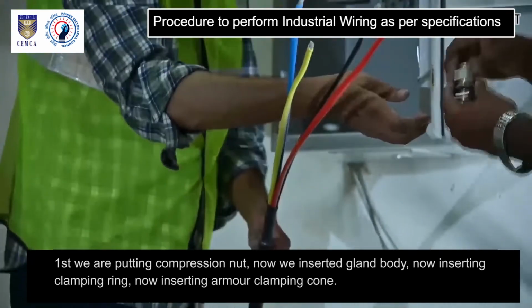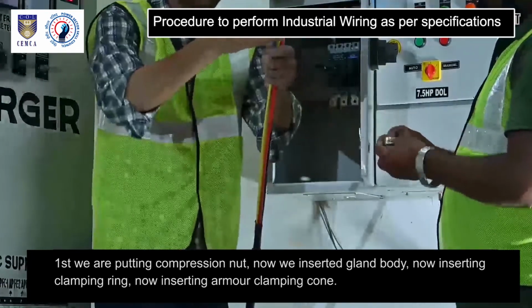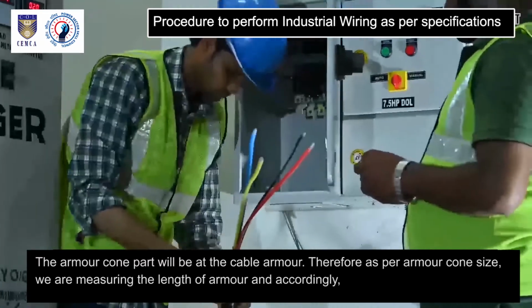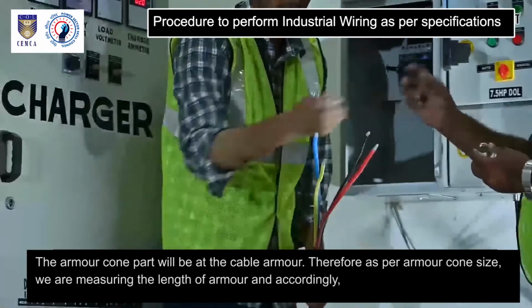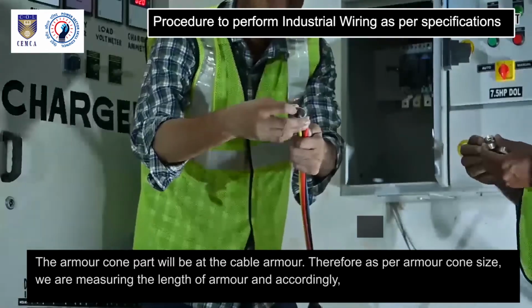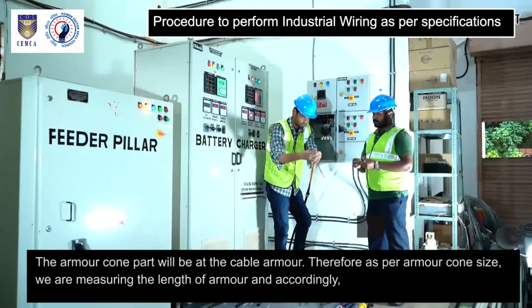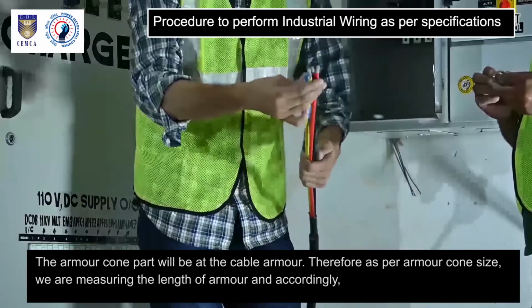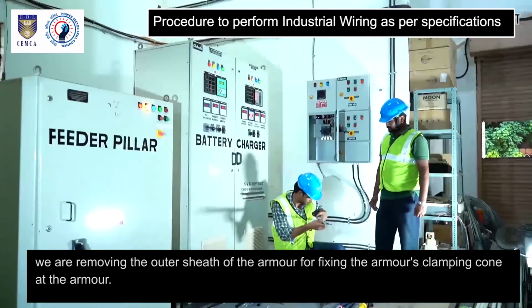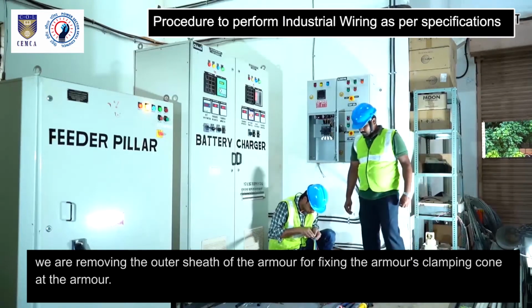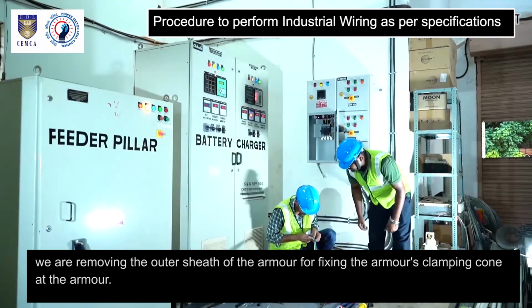Now inserting clamping ring. Now inserting armor clamping cone. The armor cone part will be at the cable armor. Therefore, as per armor cone size, we are measuring the length of armor and accordingly, we are removing the outer sheath of the armor for fixing the armor's clamping cone at the armor.